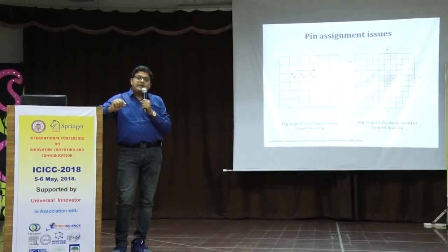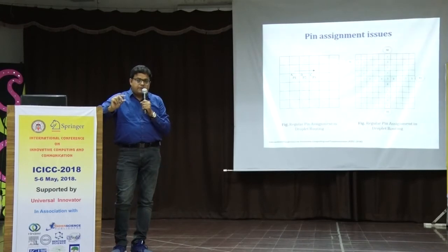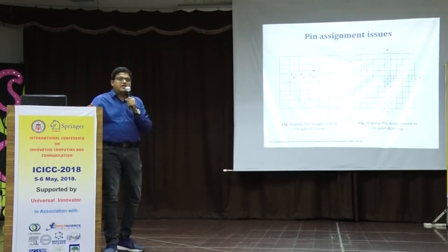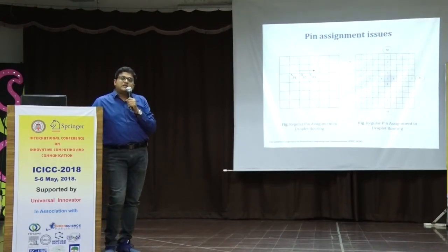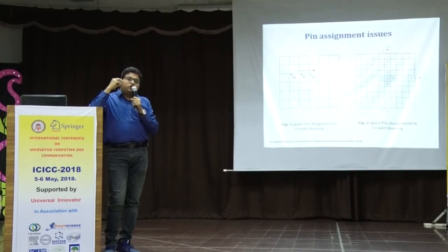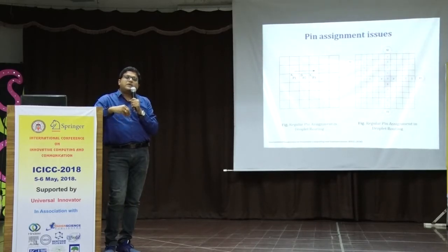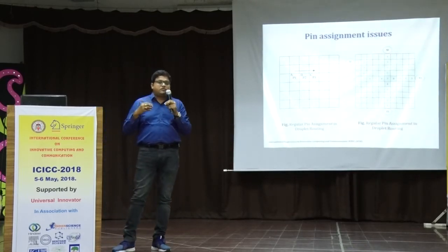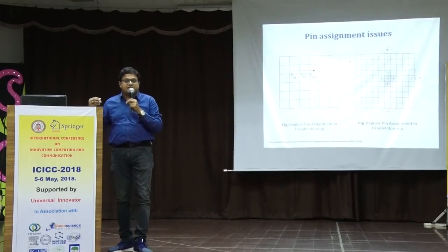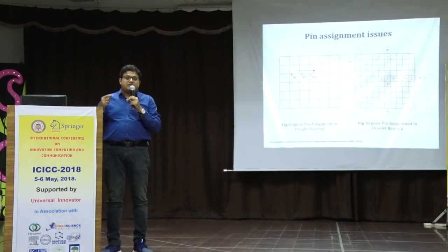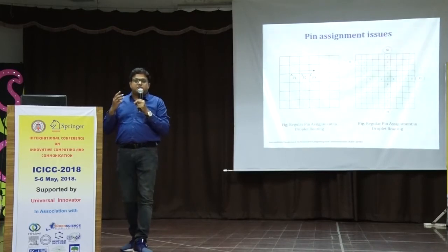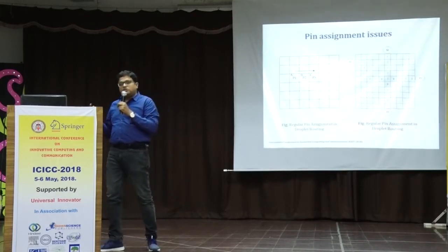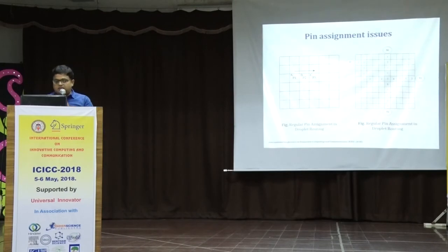That will charge the C region with the high voltage, and it will also pass on a high voltage to the region A. So with the droplet residing at B, both sides of B, A and C, will be charged with the high voltage, and then the droplet will be split from B. Some portion will be split towards A and some portion towards C, and that will make trouble. So that's why at least we require 3 different pins to maintain cross-referencing addressing with consecutive addressing.